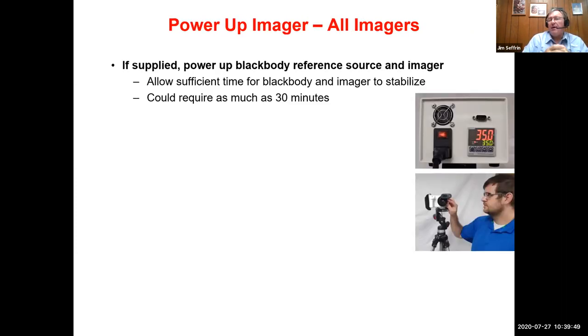Next thing you want to do, regardless of your imager type, is you're going to power up your imager. If your imager is supplied with one, you power up your blackbody reference source and the imager. Make certain that you allow sufficient time for the blackbody and the imager to stabilize. Depending upon your instrument, this could take as much as 30 minutes.